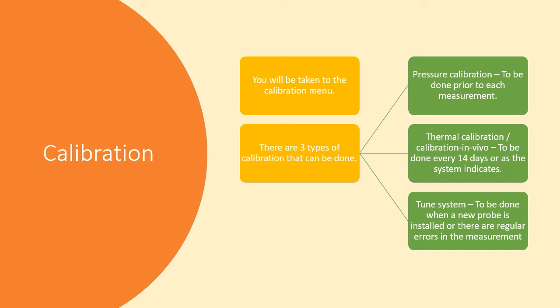After clicking on the Calibration button, you will be taken to the Calibration menu. There are 3 types of calibration that can be done. Pressure calibration should be done prior to each measurement. Thermal calibration, also known as calibration in vivo, has to be done every 14 days or as the system indicates. Tuning the system has to be done when a new probe is installed or if there are regular errors in the measurement.